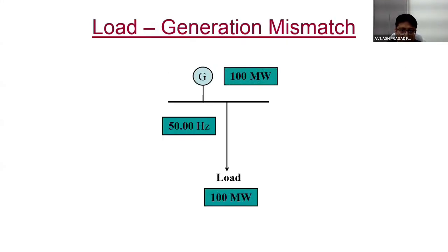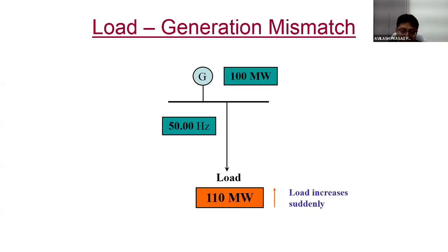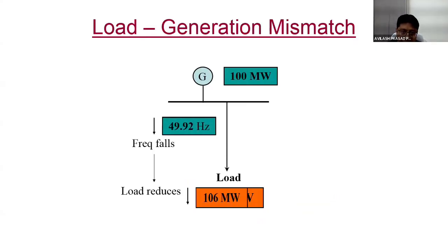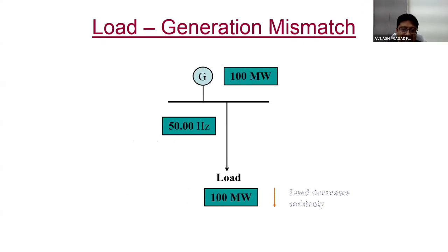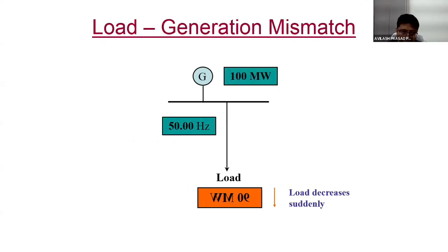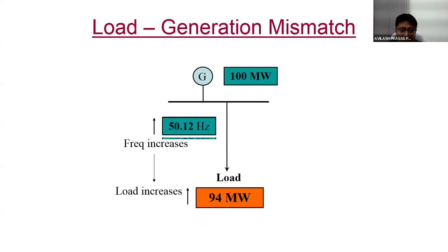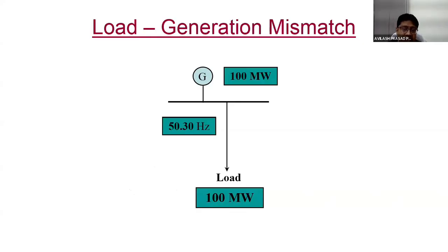If we show through the diagram that our generation is 100 megawatt at a frequency of 50 hertz and the load is 100 megawatt, and suddenly the load increases, then automatically the frequency starts falling to match the load, and ultimately it reduces to match the load and it gets stabilized. Similarly, if there is a load generation mismatch due to decrease of load, then again there is a tendency for the frequency to increase to balance the load. And it gets stabilized when the load is balanced.